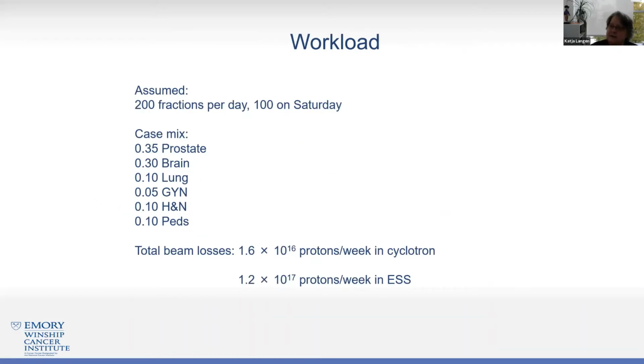So when we constructed our facility, we assumed we're treating 200 fractions per day, and we also assumed that we're treating half day on Saturday. And this was our case mix: prostates, brain, GYN, head and necks, and so on. Now, over the lifetime of your facility, of course, that mix can change. But when you start, you need to come up with a reasonable assumption that you can justify.